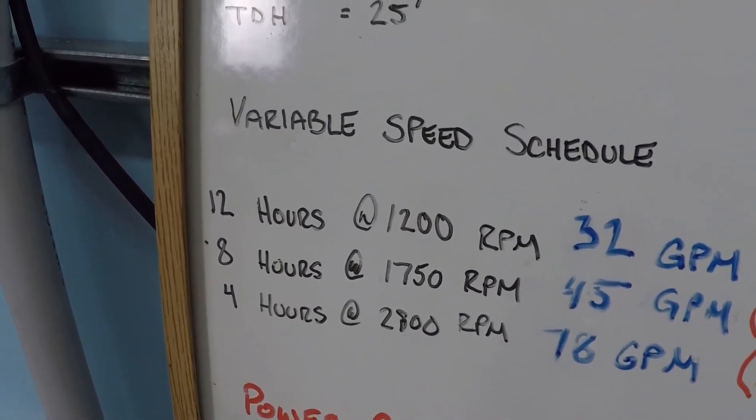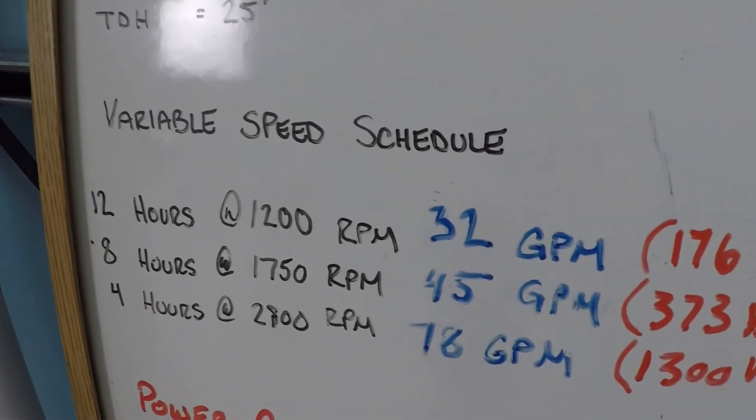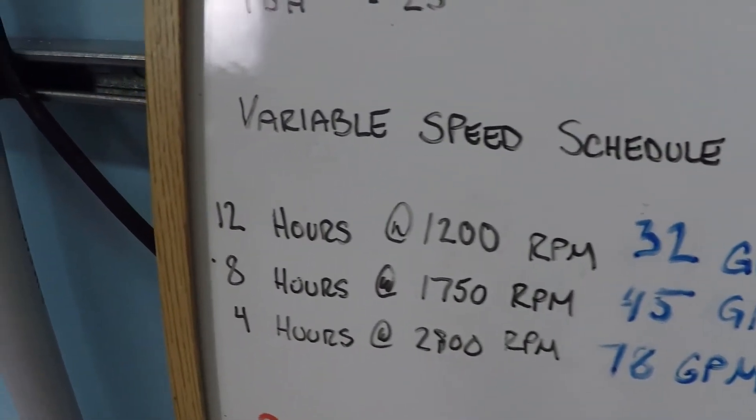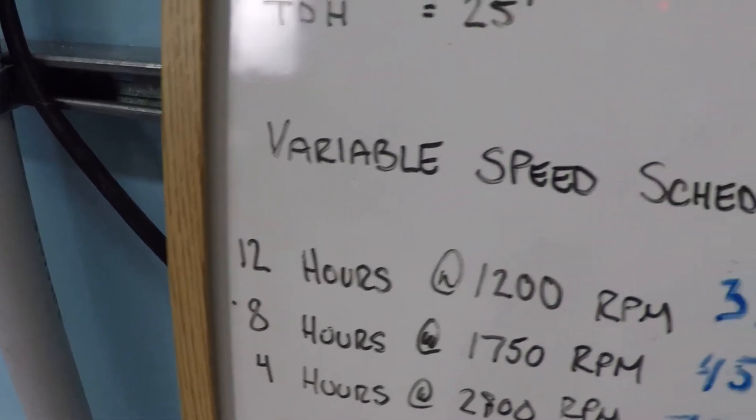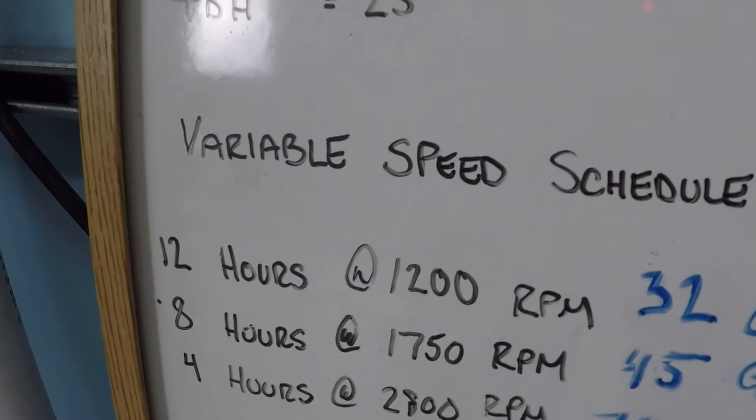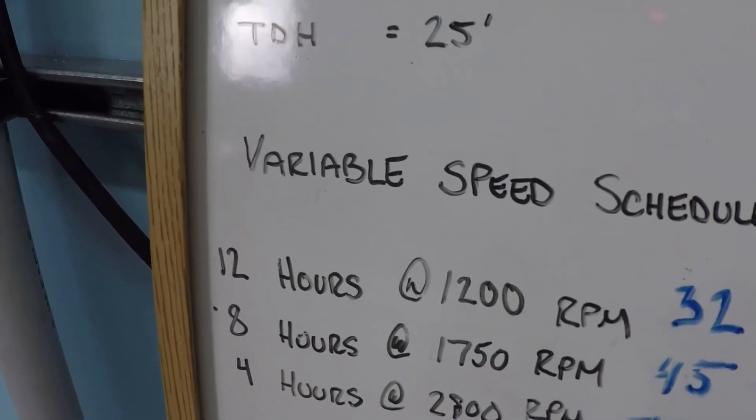That being said, I want to give you some real world numbers and that's what we've got here. So the first thing we're going to do with this variable speed pump is run it for long periods of time at a low RPM. That's very very important with variable speed pumps.